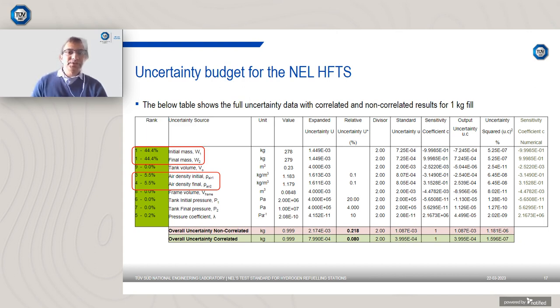The slide here shows a more detailed analysis of the uncertainty budget for a 1 kilogram fill. The key takeaway from this slide is the two areas that are highlighted in red. Essentially what we found is that the mass reading has the most significant influence on the overall uncertainty of the test rig, and it is followed by the uncertainty in the air density, which is, of course, to a much smaller extent.